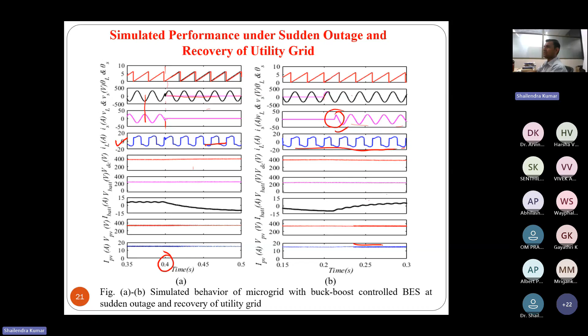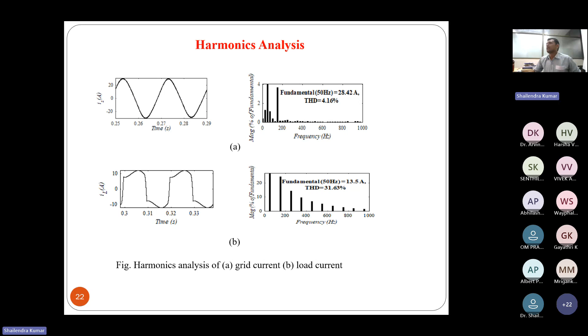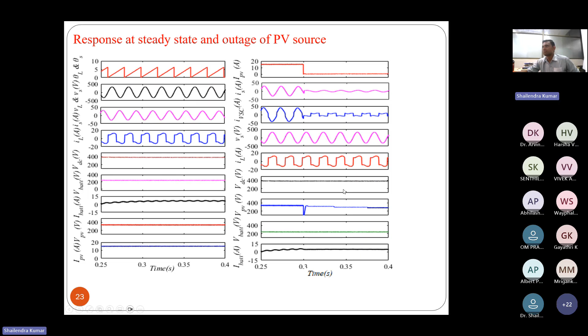These are the harmonic spectrum I was talking about. The total harmonic distortion is like 4.16%, which follows the IEEE 519 standard. However, the load current THD is around 31.63%.